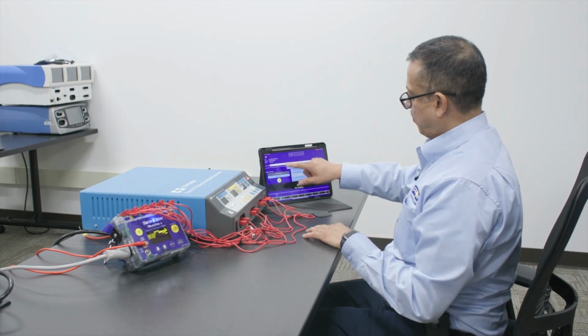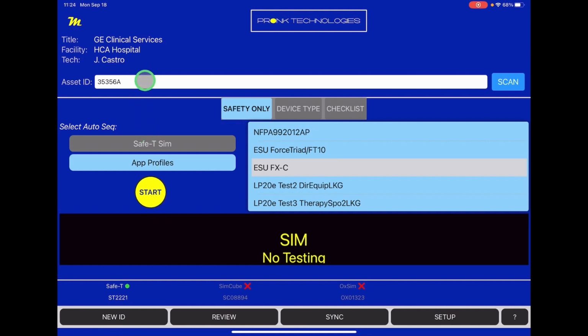And then we're going to go back to the Mobilize app, and we're going to enter in the serial number of the device under test, or if you have a barcode, you could use the scan function to scan that barcode to automatically enter it into the unit. In this case, we don't have a barcode on this device, so I've already gone ahead and entered in the serial number of the device. Now we go over to the menu here and select App Profiles so you can see all of your automated electrical safety tests that are programmed onto the Mobilize app. And we want to find the ESU FX-C sequence we want to run that I mentioned earlier that's been programmed onto the app itself. You do this, and then we have everything connected, and we're able to initiate the test and hit start.